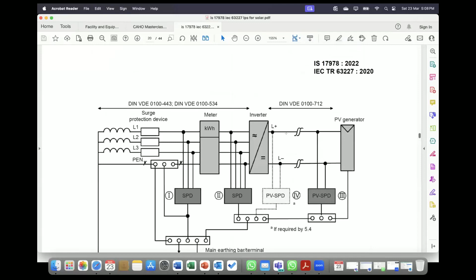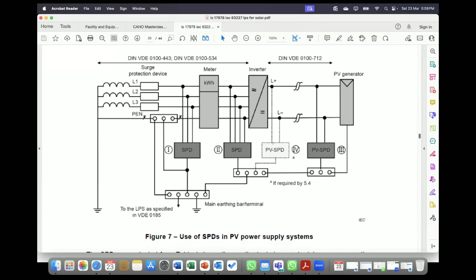Let me share my screen and show what's written in our national standard. This is from the standard published by BIS, the Bureau of Indian Standards - IS 17978:2022. You can see here, for example on the right side, the PV generator, the DC side PV SPD, and there is an equipotential bonding bar.